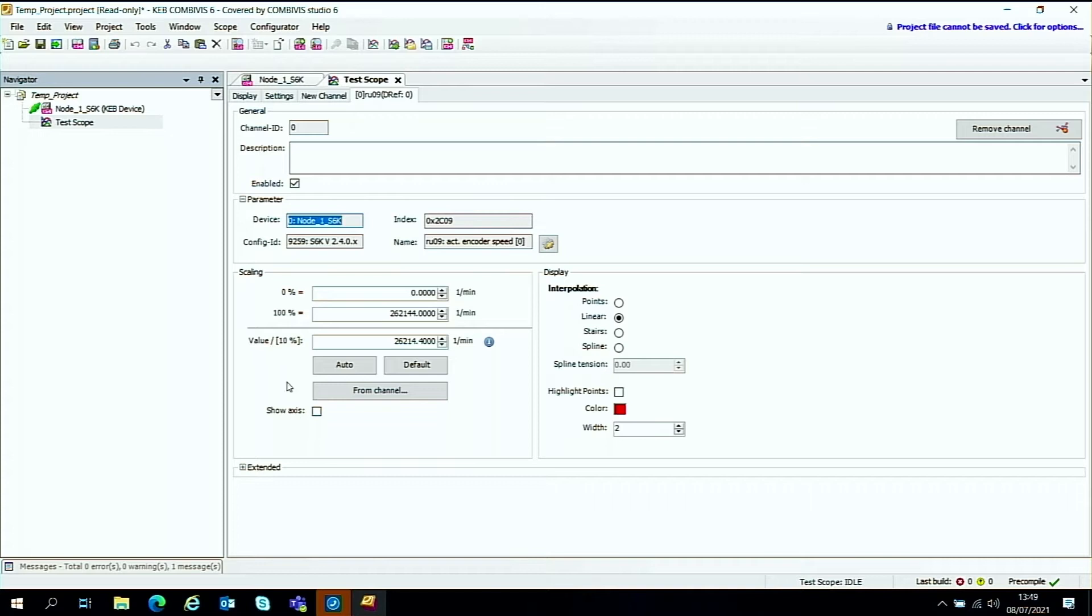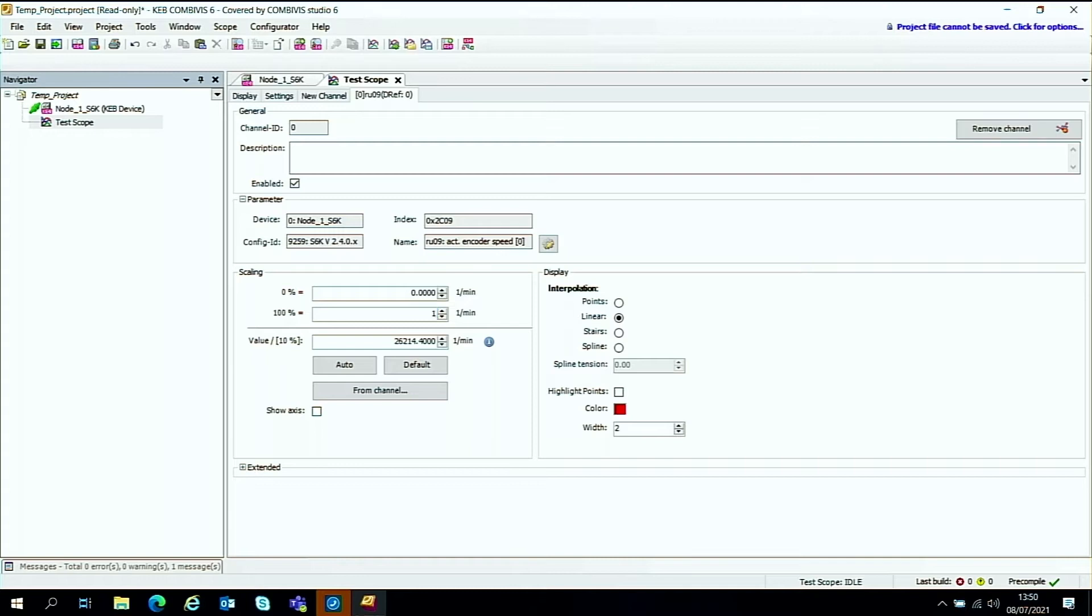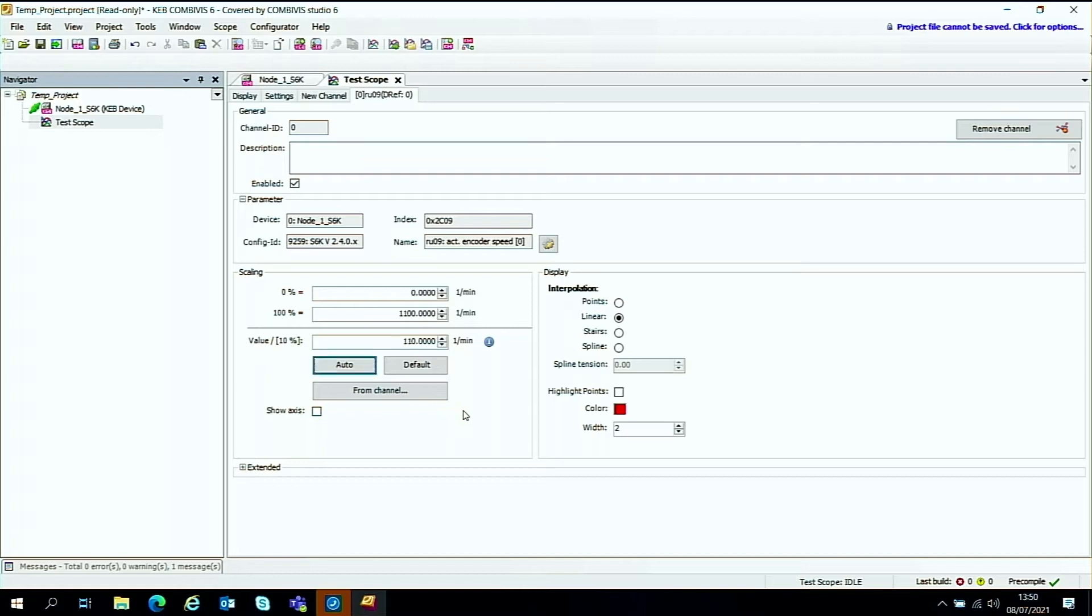And the other key thing is scaling. So the hundred percent or maximum speed that you're expecting to see from the encoder in this case, the parameters, the encoder feedback. I don't really want to go above a thousand RPM. So I will just put a one thousand one hundred in there. Just give us a bit of room and that's the scaling carried out for us for this particular channel on the scope.